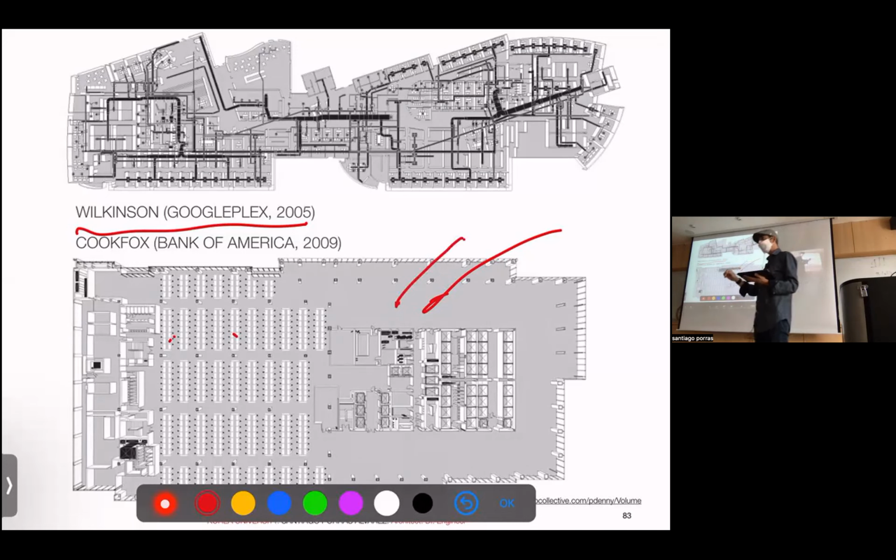This was one system in which each worker has an individual air outlet with individual control. It was like the gold standard. We're speaking of 2009, quite recent technology. Curiously, it has been one of the most inefficient buildings in terms of energy. That means that individual regulation does not solve anything. It demonstrates people are totally careless about energy and will just use it randomly. So it's not a good idea. Sounds good in theory, but it didn't work here.